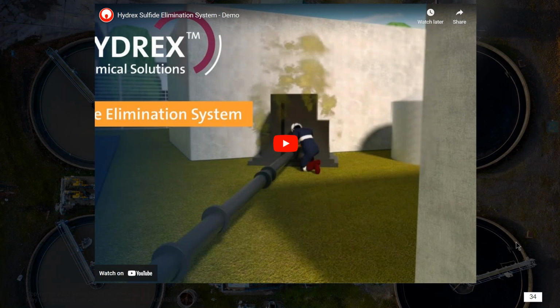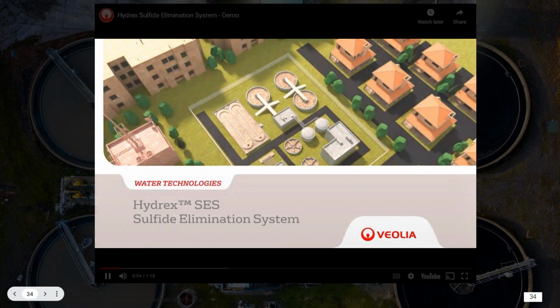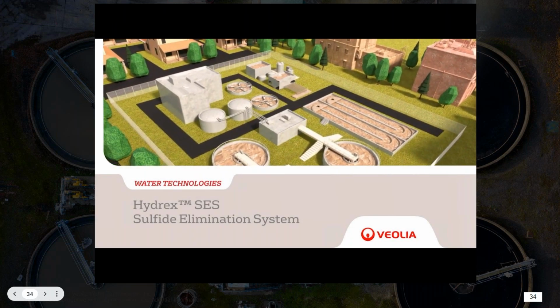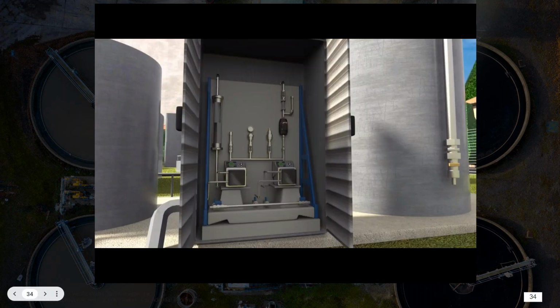I'm going to show a quick video that's an excerpt from a video you can find online on YouTube. Just Google Veolia. In a minute, we're going to see that our feed system is fairly simple, with tanks or totes for the Hydrex reactant and the peroxide. We utilize specific chemical pumps compatible with these products. We typically utilize a simple PLC to control the pumps, and where possible, we flow pace the chemical pumps in line with the wastewater flow.